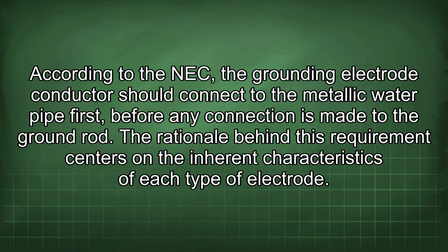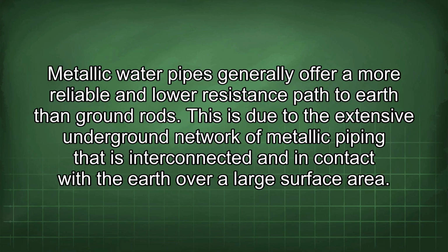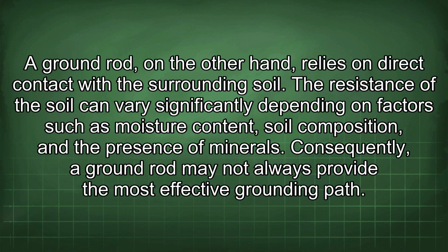The rationale behind this requirement centers on the inherent characteristics of each type of electrode. Metallic water pipes generally offer a more reliable and lower resistance path to earth than ground rods. This is due to the extensive underground network of metallic piping that is interconnected and in contact with the earth over a large surface area. A ground rod, on the other hand, relies on direct contact with the surrounding soil. The resistance of the soil can vary significantly depending on factors such as moisture content, soil composition, and the presence of minerals. Consequently, a ground rod may not always provide the most effective grounding path.